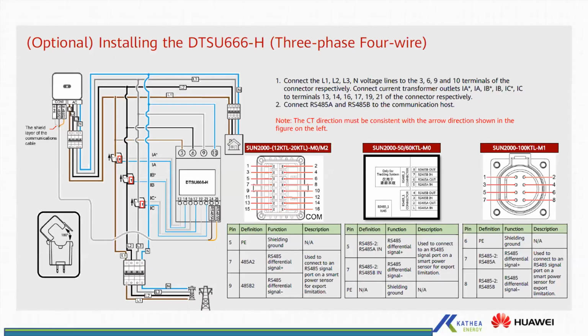And then for the HUAWEI smart meter, which is the DTSU666-H, as I've said, it's limited to a 250 amp incomer breaker size or 170 kilowatt plant size.